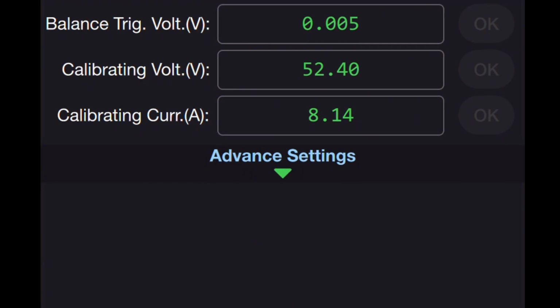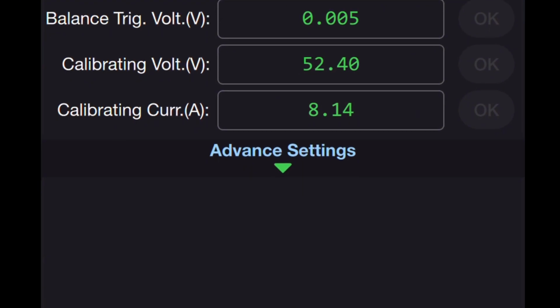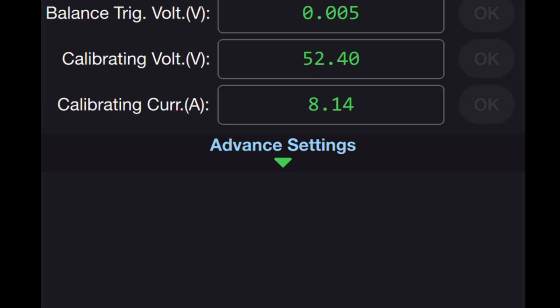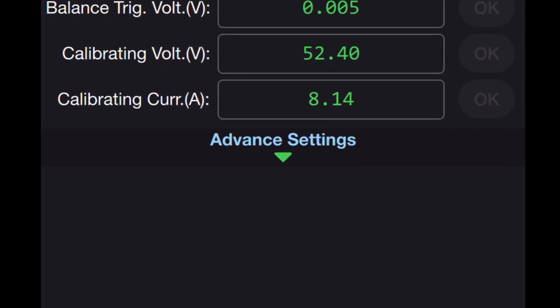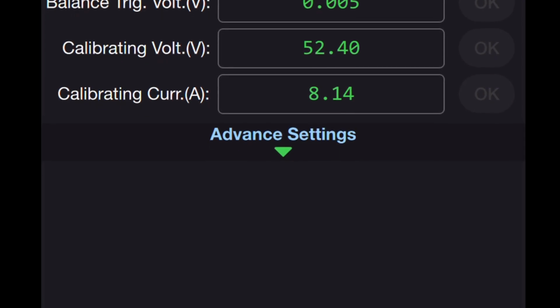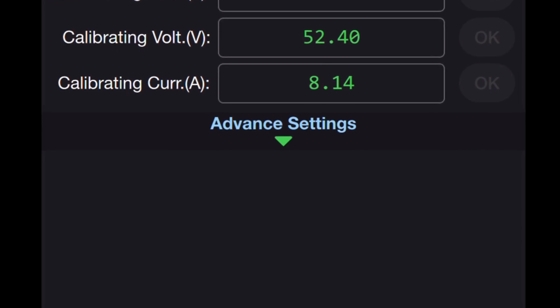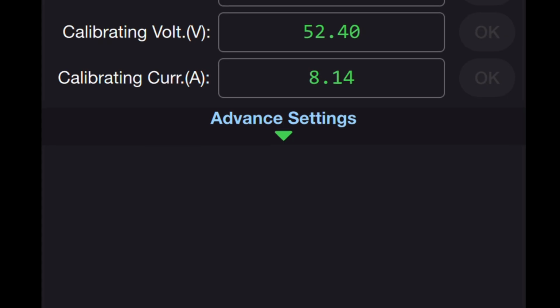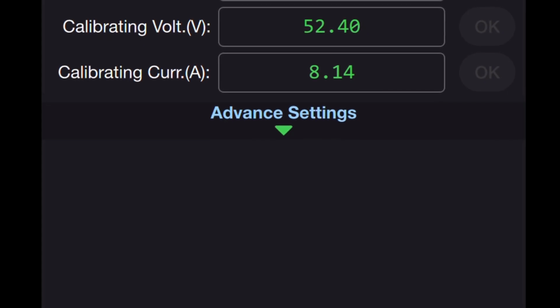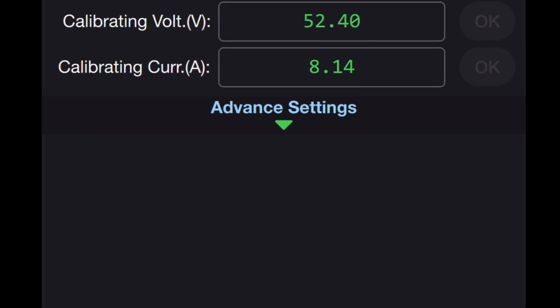Then you do a draw or a charge on the battery and adjust the amperage to be accurate also. Once you do that, the BMS calibration is complete, and it can more accurately calculate the state of charge as it goes forward, because without the right voltage, battery size, or amperage being detected as it comes in and out of the battery, it won't be accurate and it'll be off more than normal.